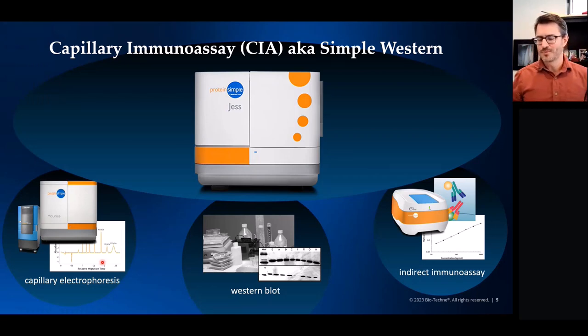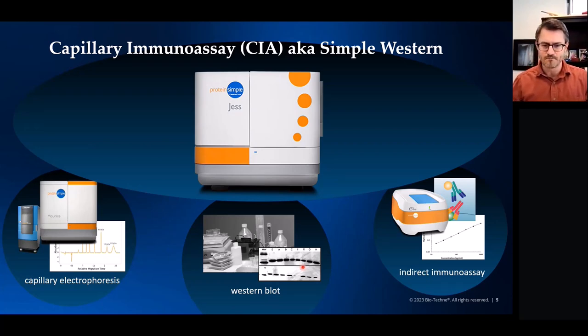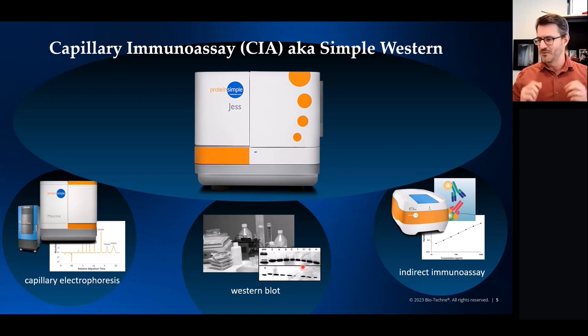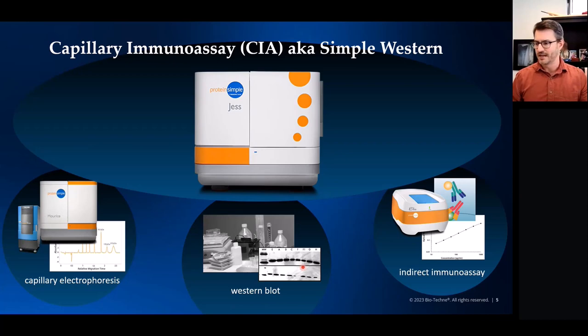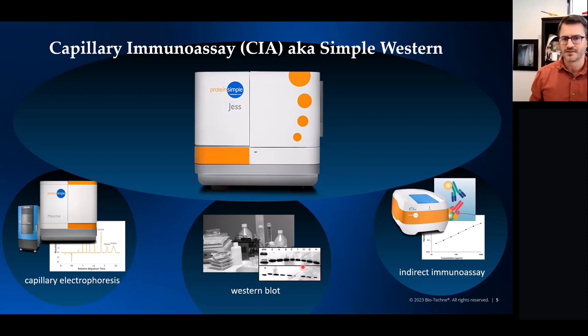It's more appropriate to call Simple Western a replacement for western blot than to call it a western blot. Western blotting involves transferring protein from a gel to a membrane — we literally do not do that step in Simple Western, because it's one of the biggest sources of variation. By definition, we are not an automated western blot; it's more appropriate to refer to us as an indirect immunoassay inside a capillary. The name bubbling to the top right now is capillary immunoassay, or CIA, though capillary nano-immunoassay, or CNIA, also appears in publications.